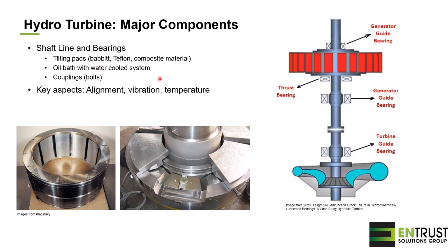Another significant, important area on the shaft line is the coupling. Here and also at the generator, it's important to have a look at the bolts from time to time. So the key aspects of the shaft line are the alignment, the vibration, and the temperature that will be monitored throughout the operation of a project.